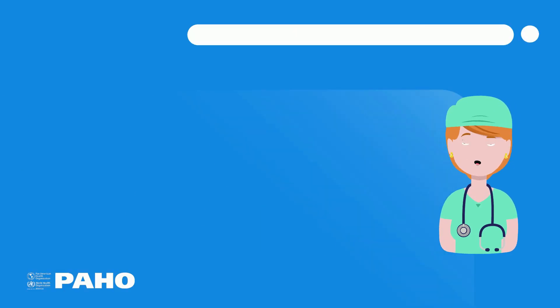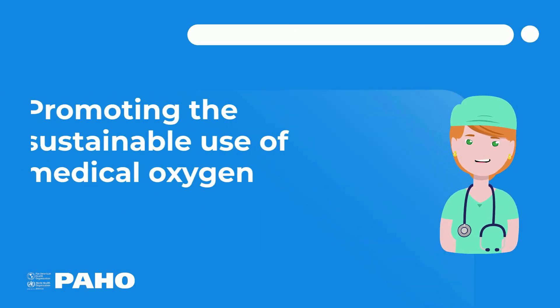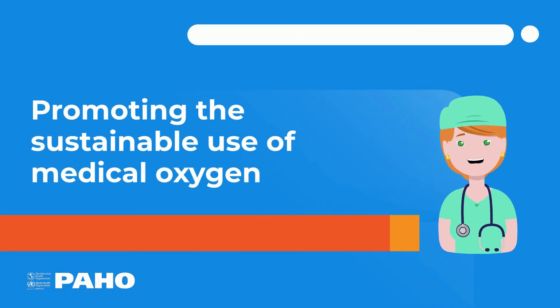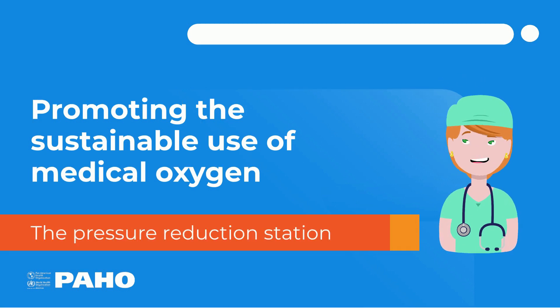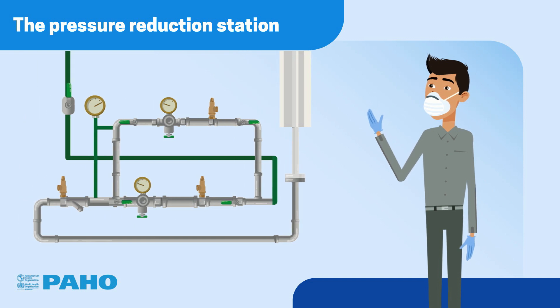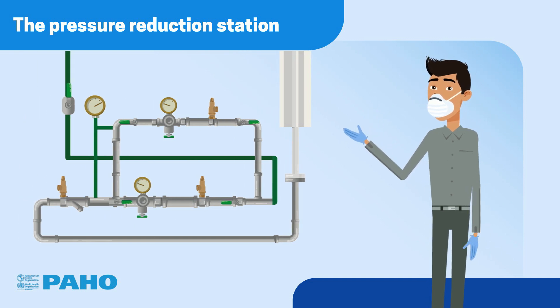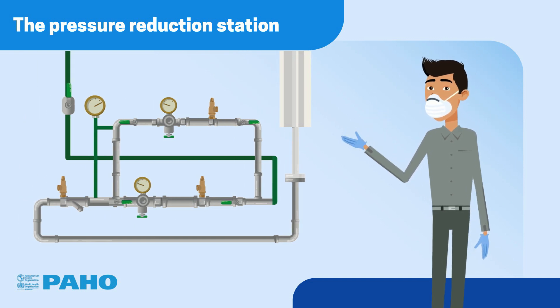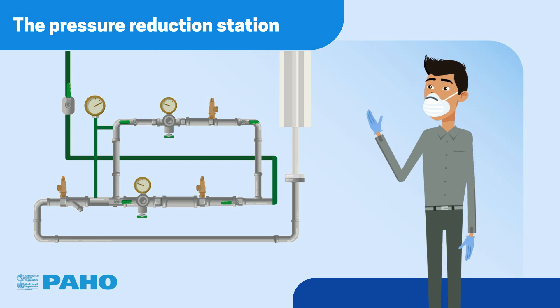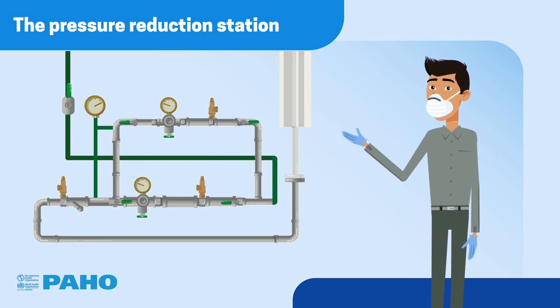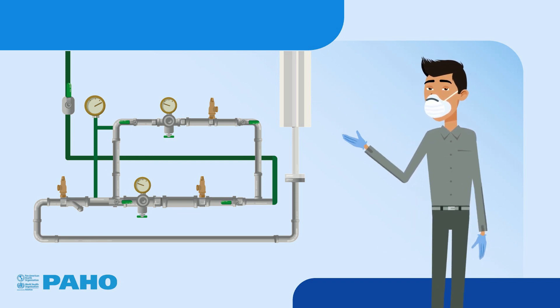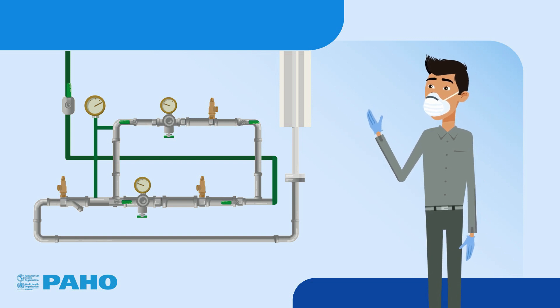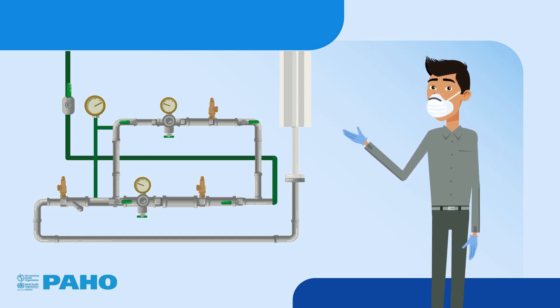This video is part of the series promoting the sustainable use of medical oxygen. Today we introduce the pressure reduction station. After the oxygen is vaporized, its pressure needs to be controlled. A pressure reduction station is used for this purpose. The station must be able to reduce the pressure of the gas and ensure the required flow to the hospital.